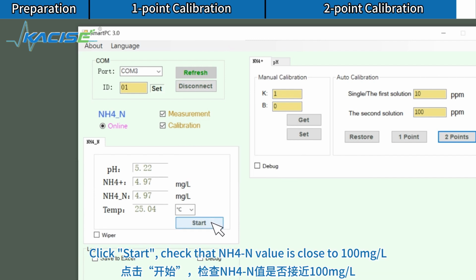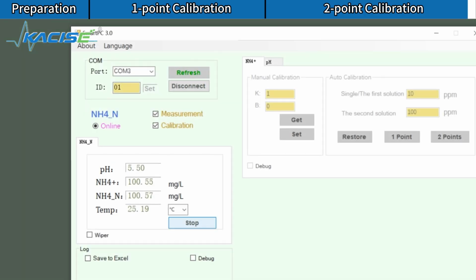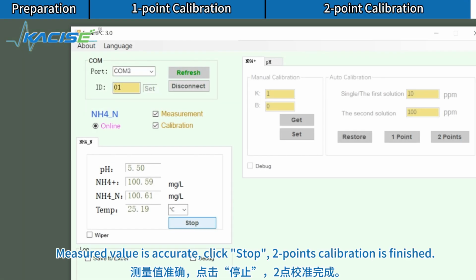Click Start. Check that the NH₄-N value is close to 100 mg/L. Measured value is accurate. Click Stop. 2 points calibration is finished.